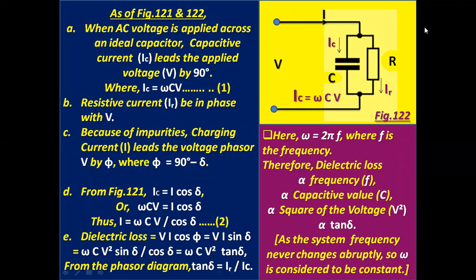See the figure. As of figures 121 and 122, when AC voltage is applied across an ideal capacitor, capacitive current IC leads the applied voltage V by 90 degree, where IC equals omega CV. Resistive current IR is in phase with V. Because of impurities, charging current I leads the voltage phasor V by phi, where phi equals 90 degree minus delta.